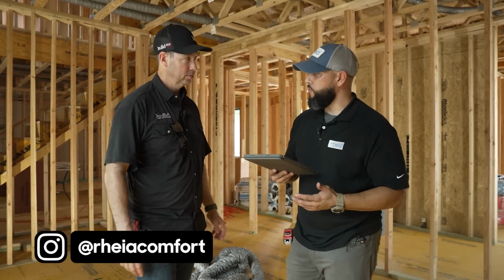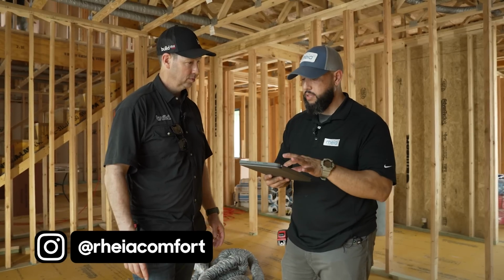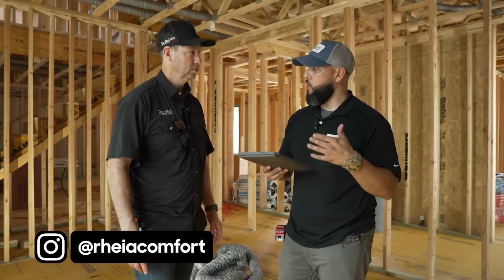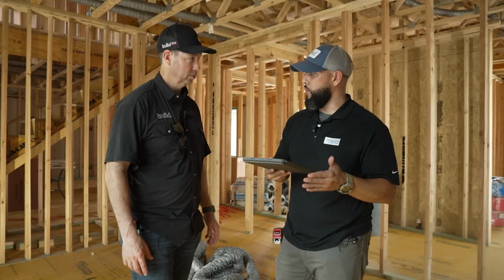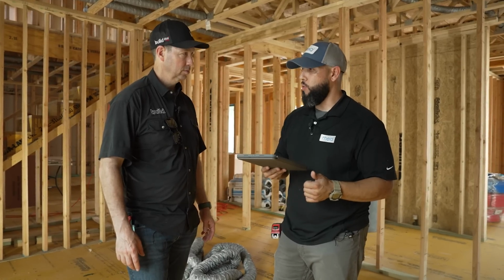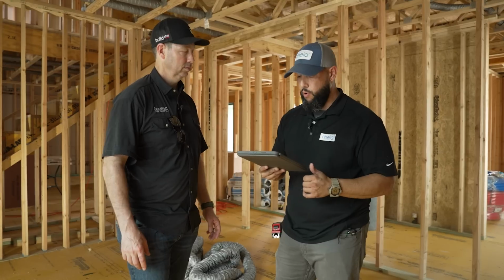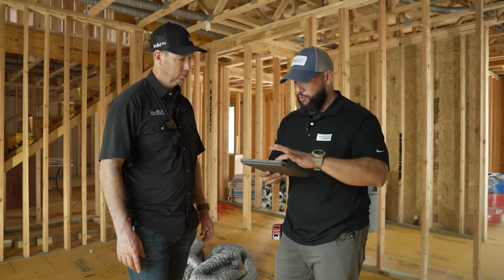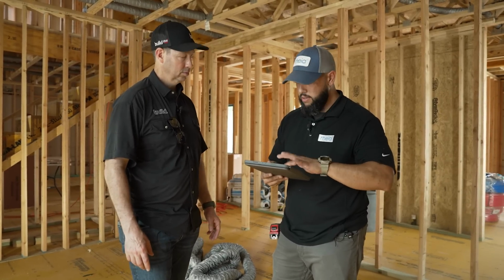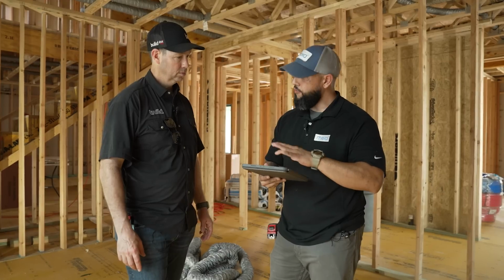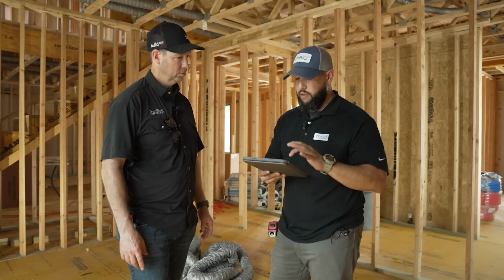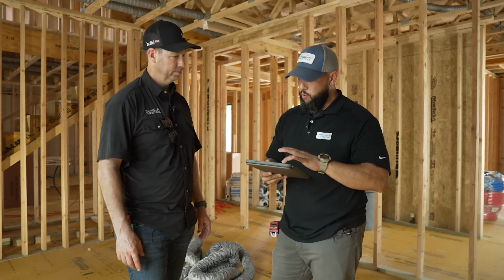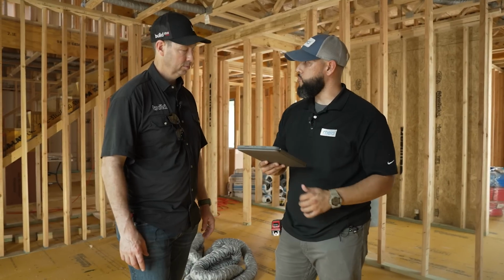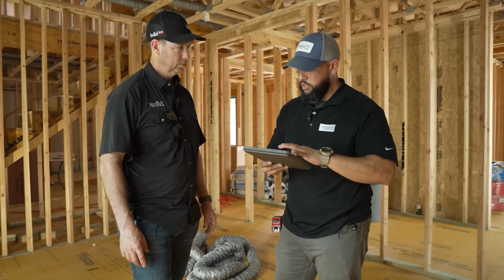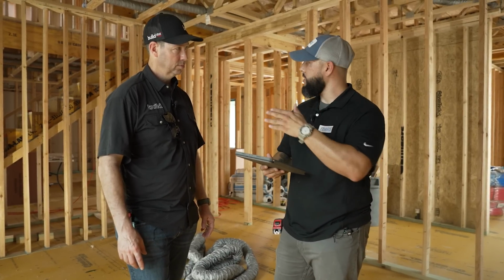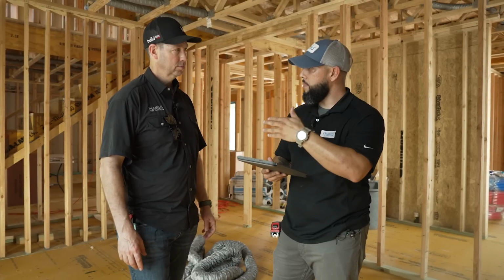So we follow a thoughtful design process, and what that means is we'll take them through Wrightsoft, and we'll go through an actual design with Rheia and our Rheia plugin through Wrightsoft. So we have our third-party designers that do that work for us, and what they'll do is they'll put these ducts in conditioned space, and it'll spit out a Manual J. We still follow all the same design parameters as a conventional system, and that Manual J will spit out these duct runs in conditioned space. And so with those duct runs in conditioned space, we could then predict each run's length, pressure drop, and CFM.